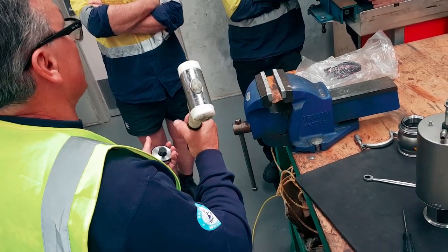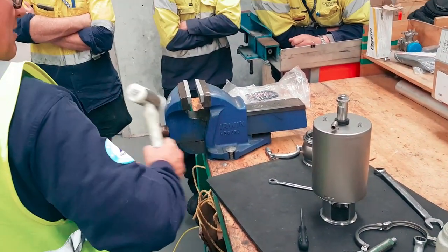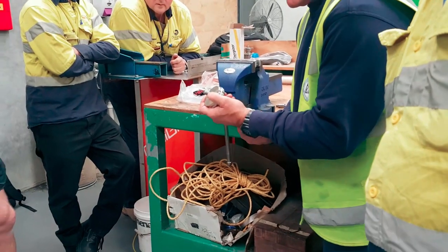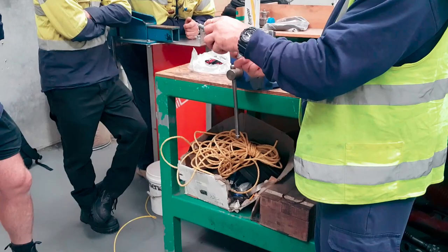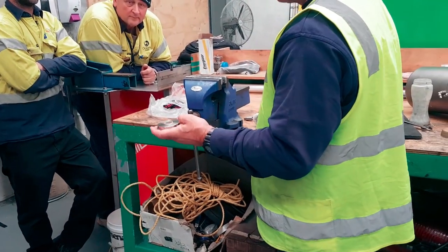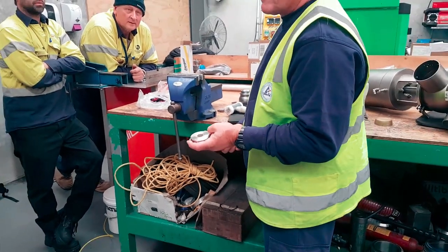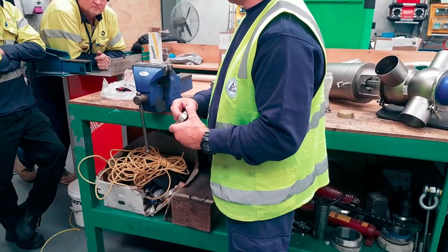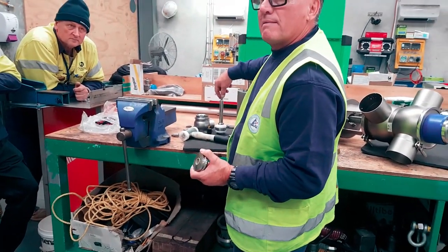You heard it? That was that last one. I've done it so many times, I just know when to stop. If you smack it any further, the dents you put on there start making a nice little helix that corresponds with this. So therefore, just be careful. Your seam bush does not come in the kits. It's only a change-of-wear part later on. But again, keep yourself some handy just in case. If that's getting smashed in there, start looking at the plug, what state the plug is in.